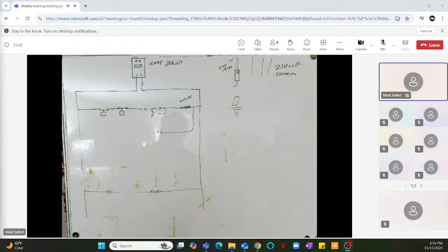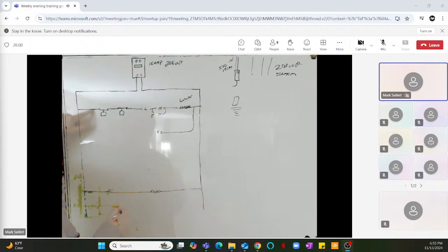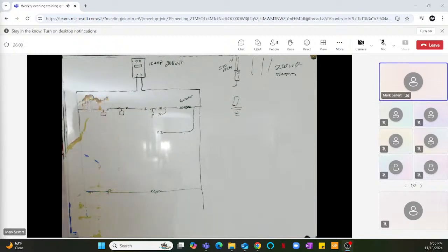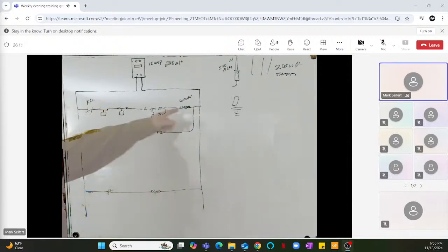On this diagram, if the low pressure opens or the high pressure opens, it kills the circuit. Contactor turns off. Of course, we can put a relay output in here. So let's just do that, because that's what we work on a lot. Relay output, RO. So that's controlling your compressor. And that's it. That's how it works.